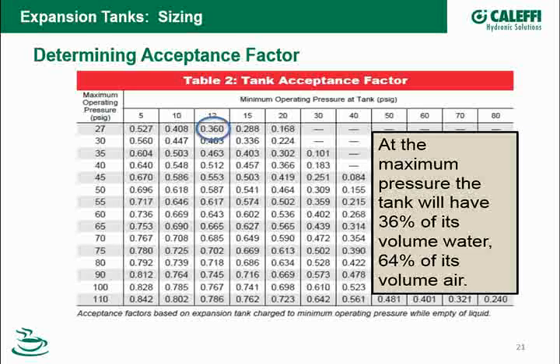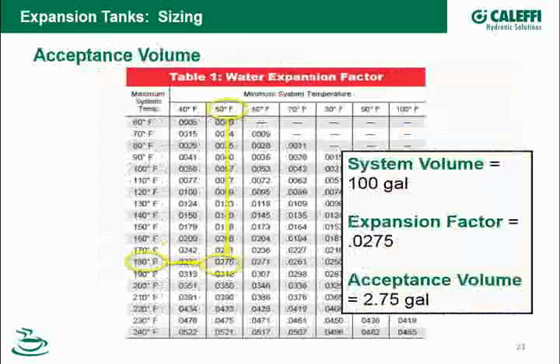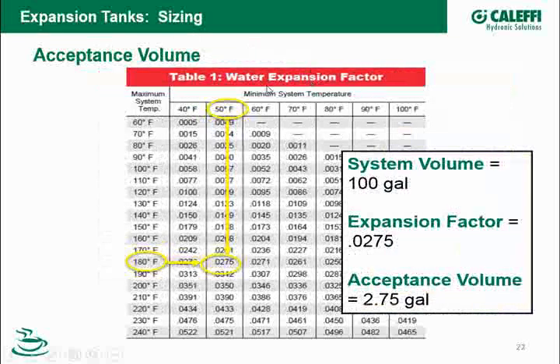Very good. Okay. So I have my pressures, which will tell me what percentage of the tank's volume I can use storing the expanded water. Now I have to look at how much expanded water it needs to hold. So it's back to that chart we looked at before, with minimum system temperature here, maximum system temperature here. If I'm going for a total hands-off system, where I'm filling it and not draining anything, so 50 degree minimum temperature, 180 degree maximum temperature, there's that 0.0275 expansion factor. Again, if I have 100 gallons of water, the tank has to hold 2.75 gallons. And again, that 2.75 gallons is just the water component.